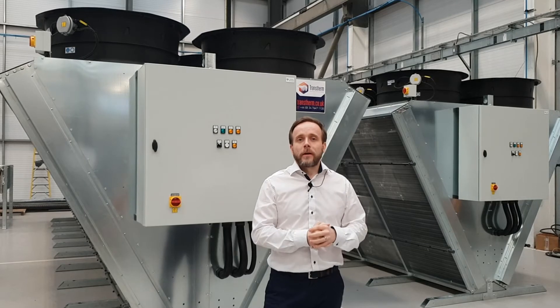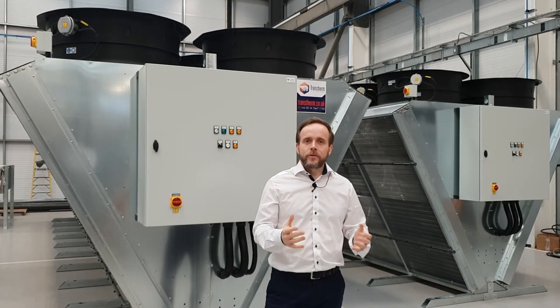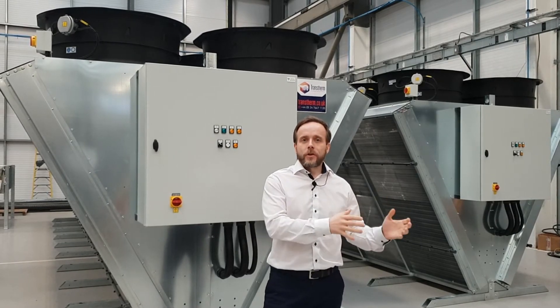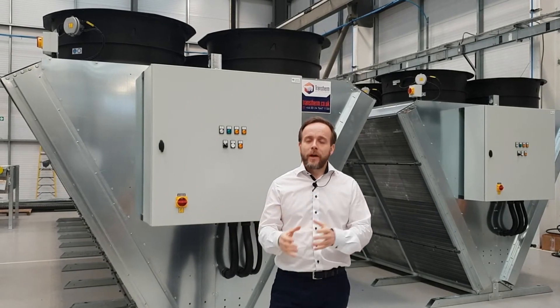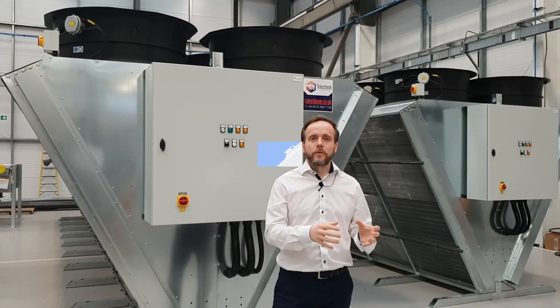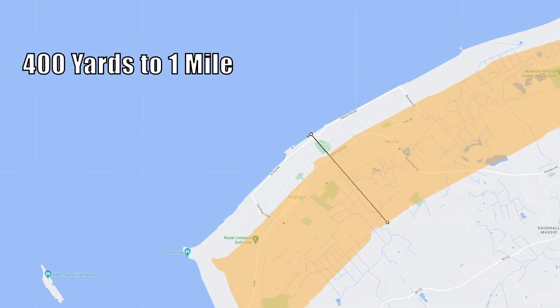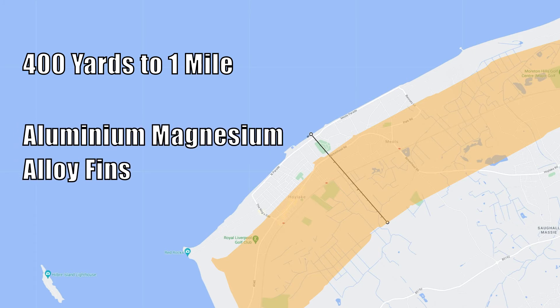The second thing that's really important about site location is materials of construction. If we are putting a piece of equipment close to the coast or in a corrosive atmosphere of one form or another, we have to make sure the build materials are the correct ones. Generally speaking, if we're further than a mile from the coast we can use standard materials — copper tubes, aluminium fins, and galvanised casework. If we're between 400 yards and a mile from the coast, there's a mild upgrade where we use an aluminium-magnesium alloy fin, which has great protection in semi-coastal applications.